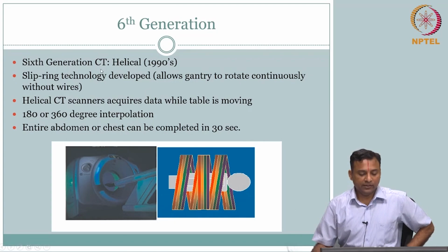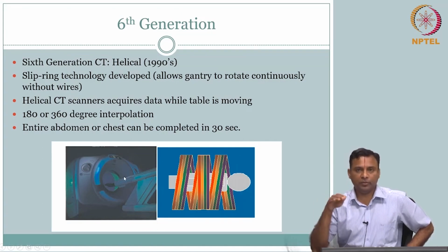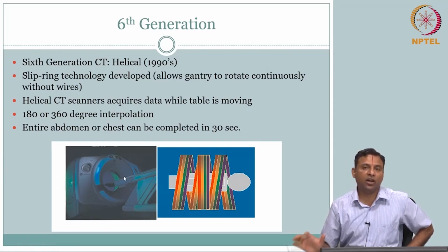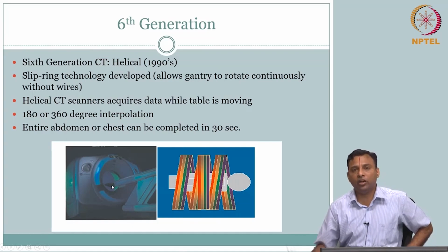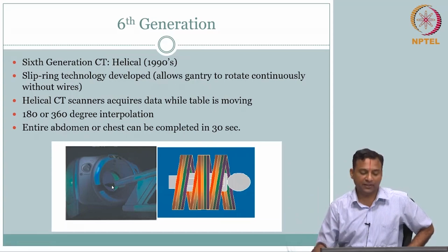Okay. So here the point is everything else is similar, but you have added this bench. Your patient bench also is part of your instrumentation for data acquisition. It is not just the patient lying. That is also technically contributing to the registration, because its position has to be recorded so that in the recon you know how it is happening. So in some sense technically it's a part of instrumentation.